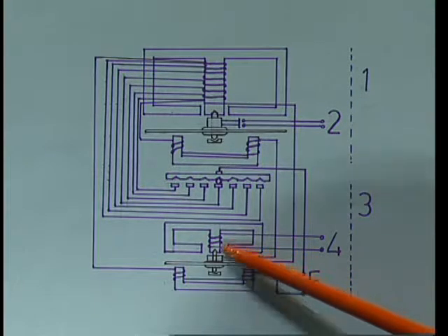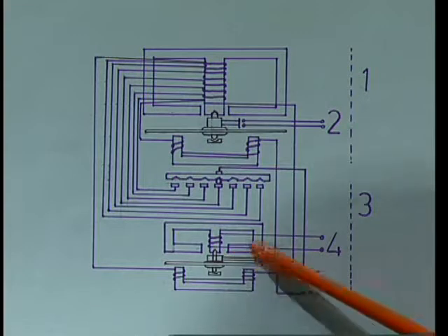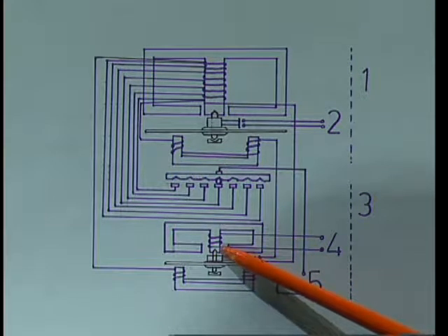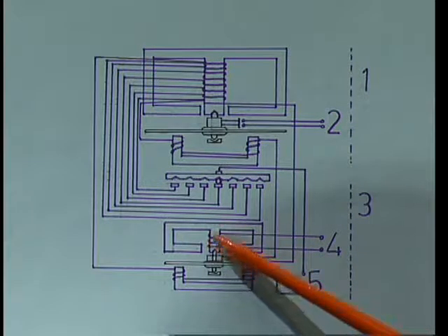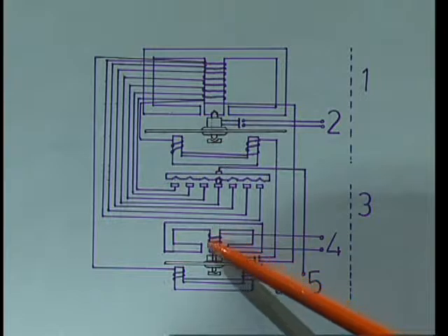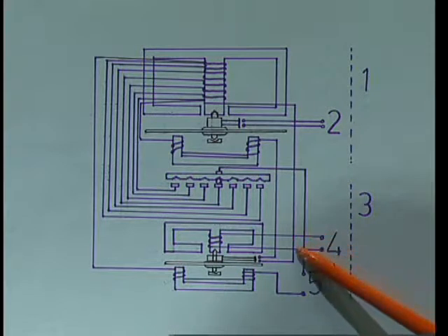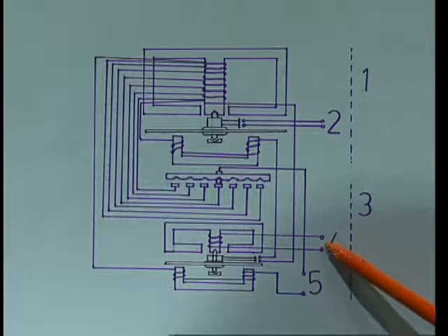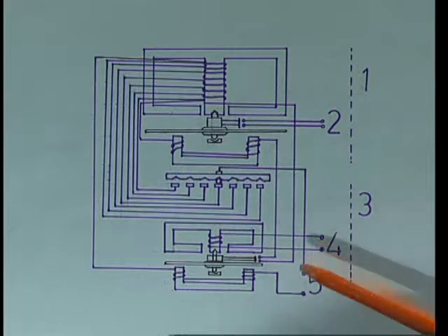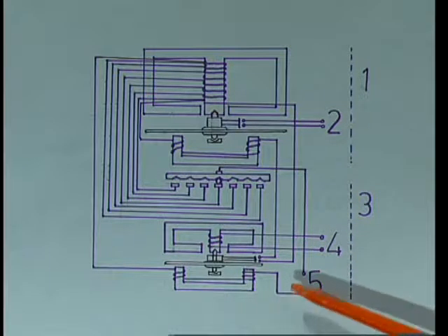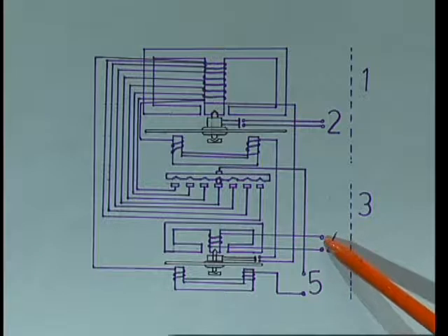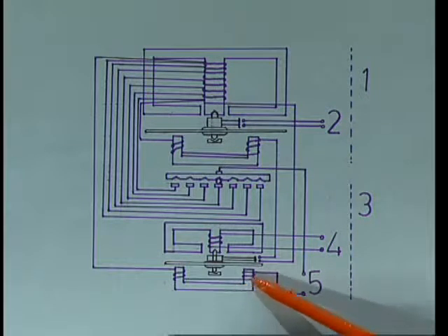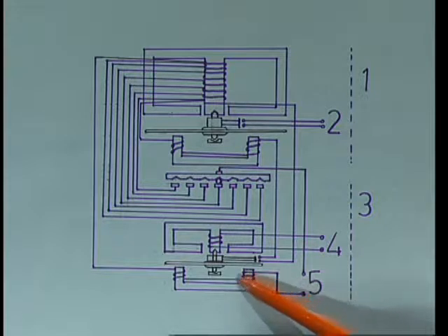First, the upper electromagnet of the directional power relay consists of a winding. This is called the potential coil, wound on the central limb, and it is connected to the potential transformer of the circuit, that is, the voltage to be protected. The voltage to be protected is connected here, and the lower electromagnet is called the current coil, and this current coil is connected like this.